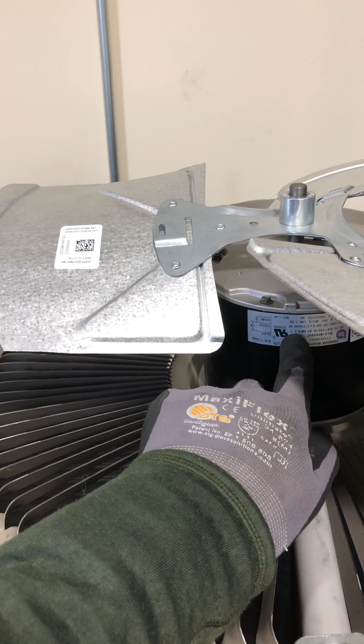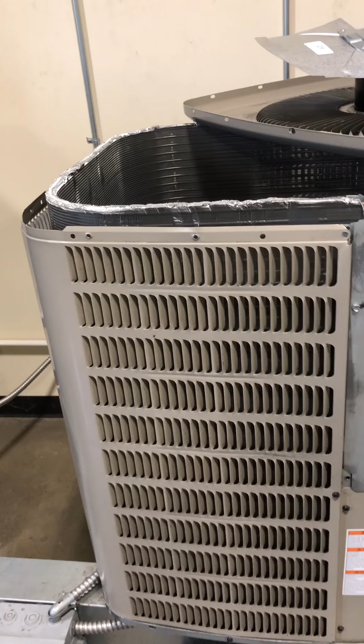All the information you'll need should usually be on the nameplate - horsepower, what type of capacitor it uses, everything like that should be labeled right there. For those of you that took refrigeration, this is the fan that's moving air across our condenser coil to cool that compressed superheated vapor, cool it back down so it condenses into a liquid and then subcools. We're using this condenser fan to pull air over that coil to make that happen. This is a very, very common change, especially if you're a residential guy - you're going to change this a lot. It's a very easy repair. We'll do it a hundred times out here, but that's our first component, the condenser fan.